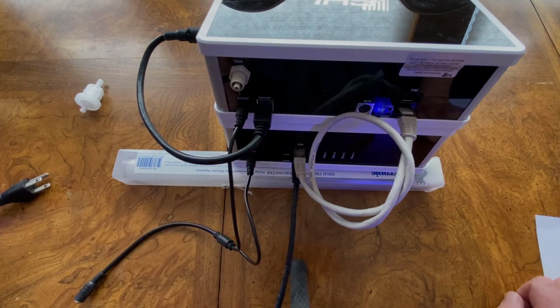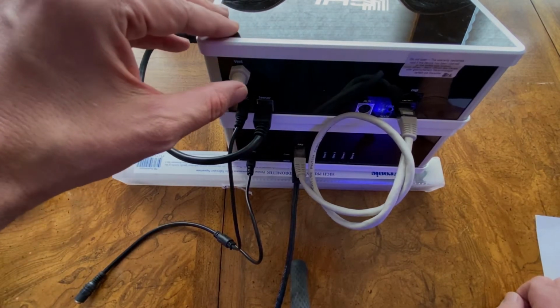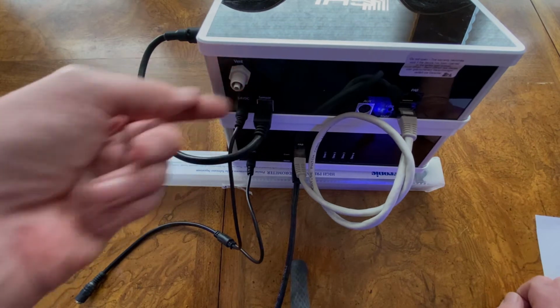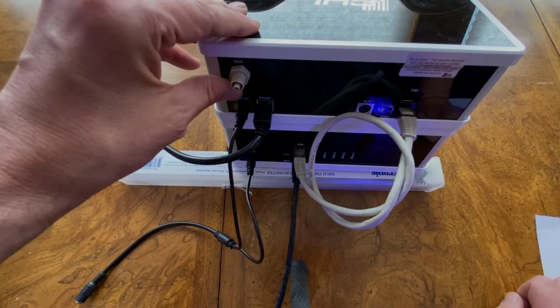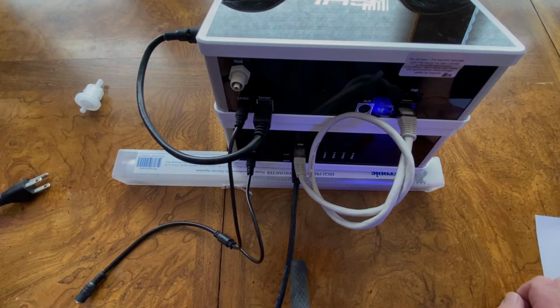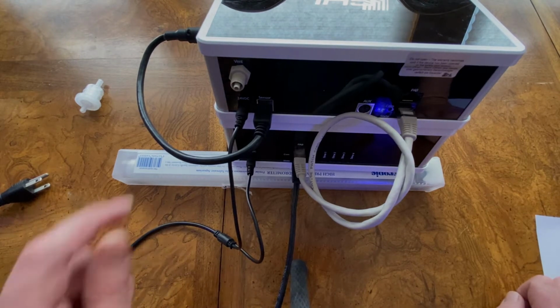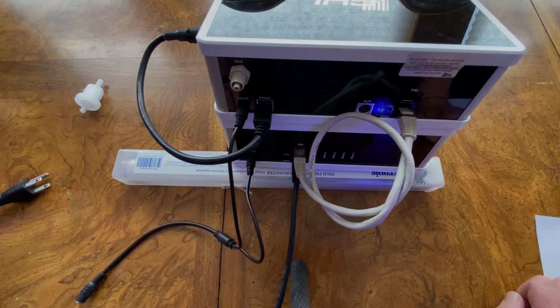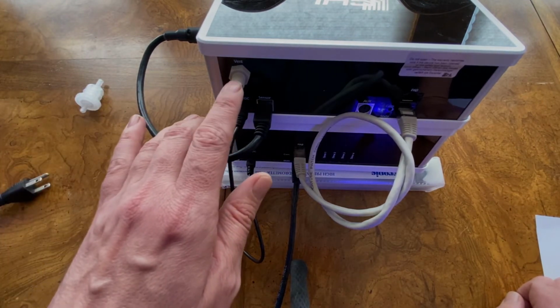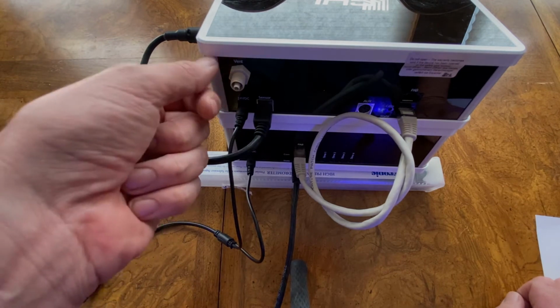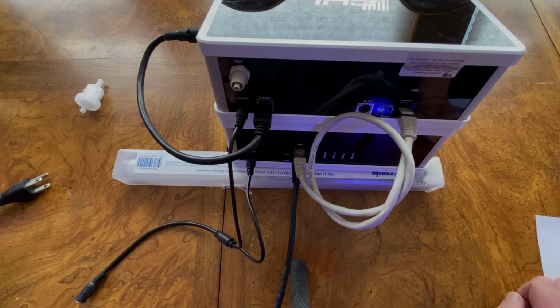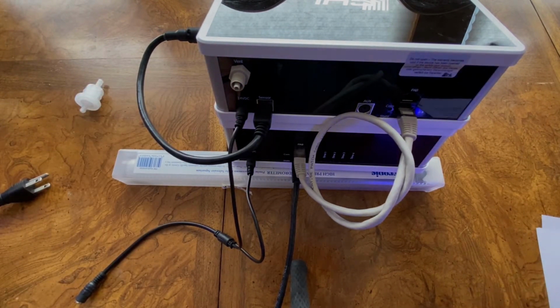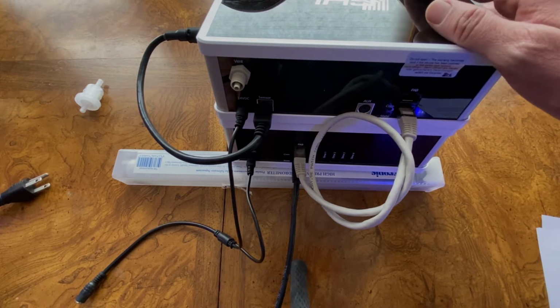The next thing you're going to want to do before you install it into your cabinet is install your vent tube. There are 3 different configurations. Number 1 is you can vent directly back into your sump. You can vent into a drain line, or you can vent into a wastewater container. The choice is yours. So what you would do is install your dosing tube here, tighten up the nut, and then that would be the installation of your vent tube. And that's all you would need to do to the back of the unit.